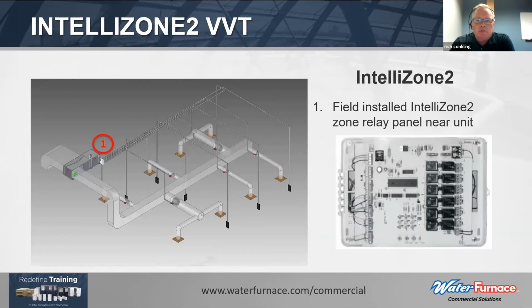At the heart of the control is the IntelliZone 2 board. It is field installed near the unit. One of the primary functions of that is to provide relay control for the individual zone dampers. It also provides us the ability to pull back information from each of the zones in terms of temperature, humidity, and other data from each of those zones.